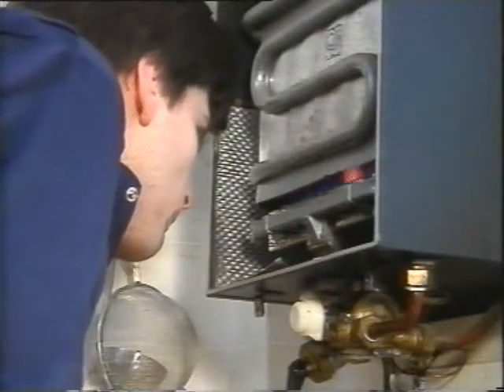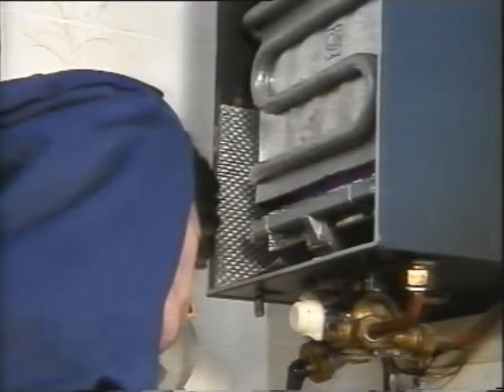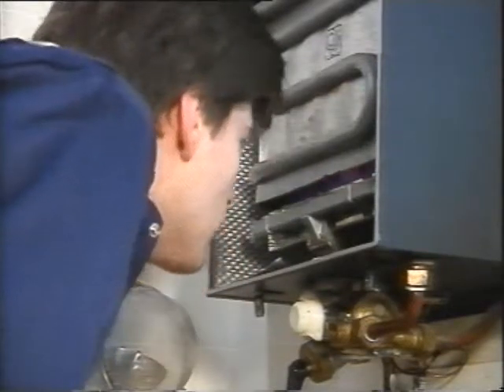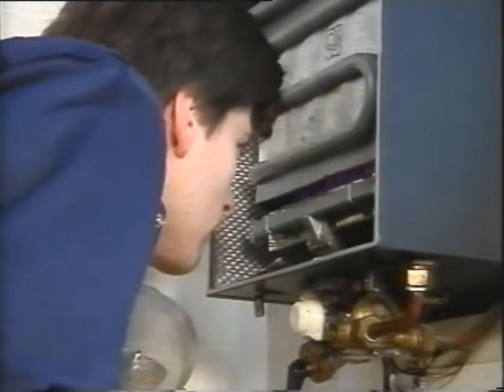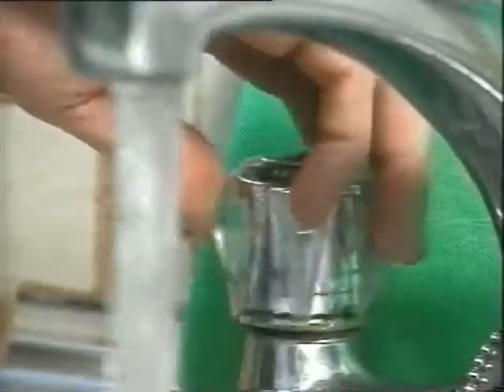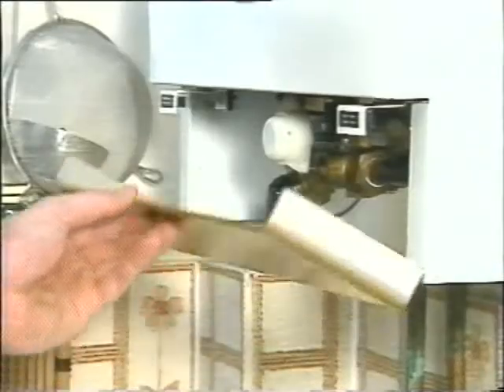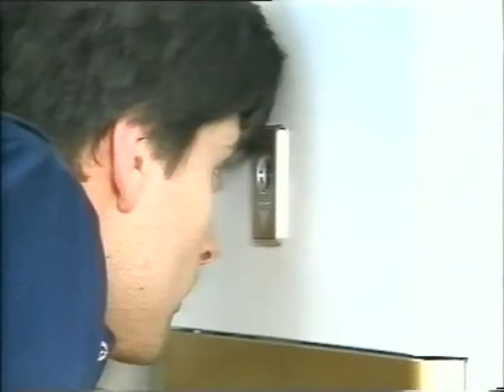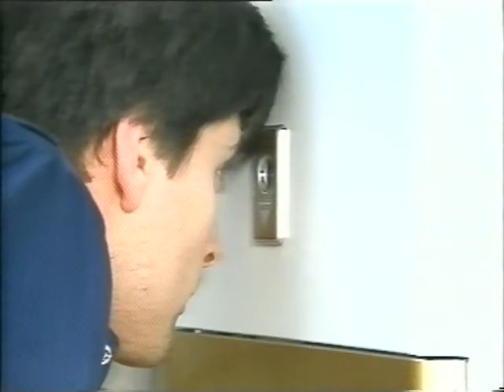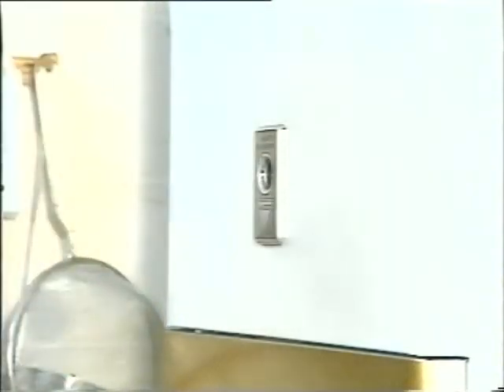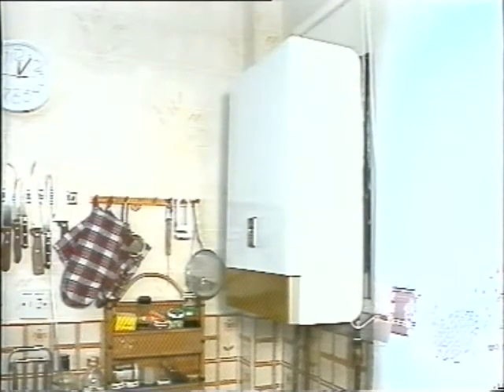The burner should ignite. Now you look at the burner. Check that the pressure's right, the connections are good, and use leak detection fluid to make sure that there's no gas escaping. When you've checked the flame picture and made sure that the water's flowing and heating up as it should, turn off the hot tap again. Then when you've turned off the pilot and checked the flame safety device, you should tell the customer how the heater works and remind them that the appliance needs servicing once a year.